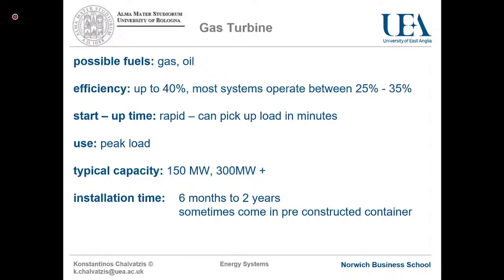Now with gas turbines, it's different because startup time can be rapid. Why? Because there's no other medium you need to transfer temperature to, you just have the fumes. You throw more fuel, more air in there, you produce more energy. It can be very fast, responding in a number of minutes, in fact even less than 1 minute. It starts ramping up electricity generation in less than 1 minute.